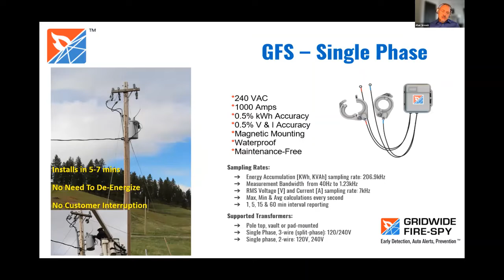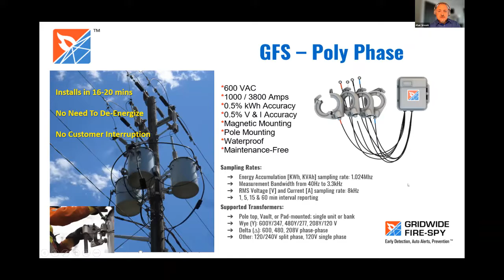The next example would be the polyphase view. It takes a little bit longer, but it's still a very fast installation process. Same story as the single phase environment, no need to de-energize the transformers or the grid in any way, therefore creating no customer interruption. This becomes very important in the polyphase market because these transformer situations are typically assigned to commercial and industrial locations, or institutions, where interruption could be really critical. So the design of the product keeps us from creating those kinds of impacts for downstream users.